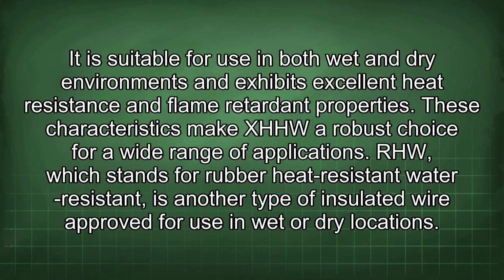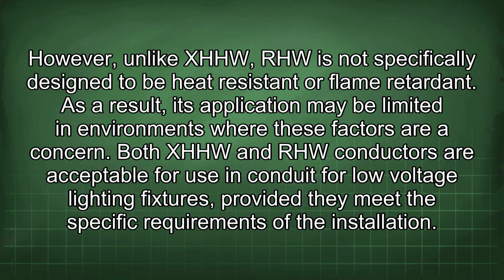RHW, which stands for rubber heat resistant water resistant, is another type of insulated wire approved for use in wet or dry locations. However, unlike XHHW, RHW is not specifically designed to be heat resistant or flame retardant. As a result, its application may be limited in environments where these factors are a concern. Both XHHW and RHW conductors are acceptable for use in conduit for low voltage lighting fixtures, provided they meet the specific requirements of the installation.